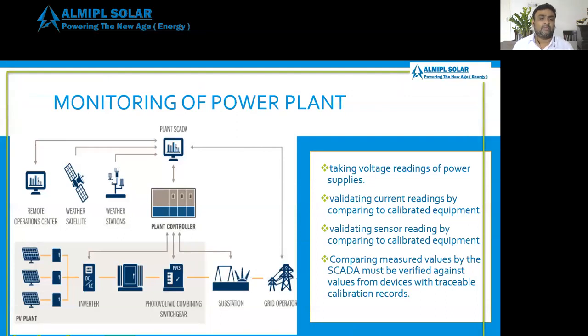Monitoring of power plants, remote operation center. All these things we can connect with our system. Weather situation and satellite, these can also be done with Google Maps. Weather station, plant SCADA, plant controller, PV plant, inverter, photovoltaic combiner switch, substation, grid operator. Take voltage readings of power supplies, validate current readings by comparing to calibrated equipment, and validate sensor readings by comparing to calibrated equipment. Measured values from the SCADA must be verified against voltage values from a device with a traceable calibration record.